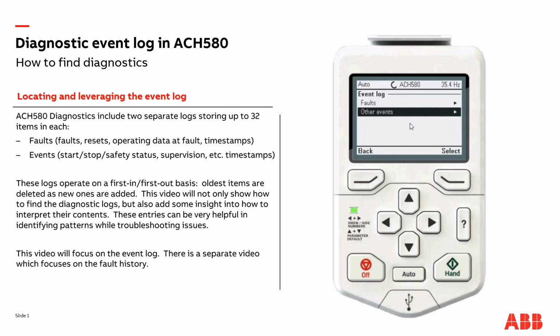Back out. What else have I got here? Oh, I've got supervision programmed in the drive. So let me raise the set point. The supervision is set for 40 Hertz. So this should trigger the supervision, which it does. So let's take a look at the event log.